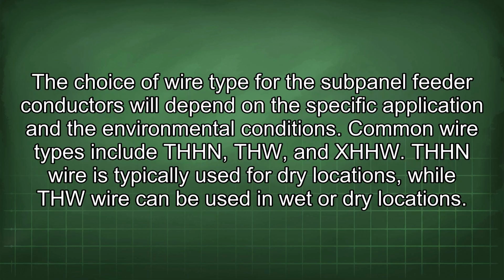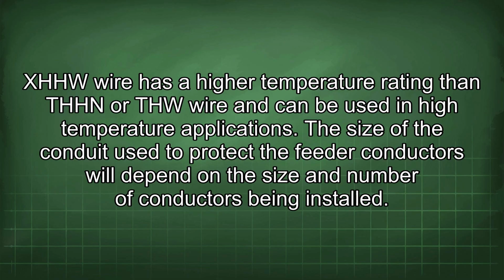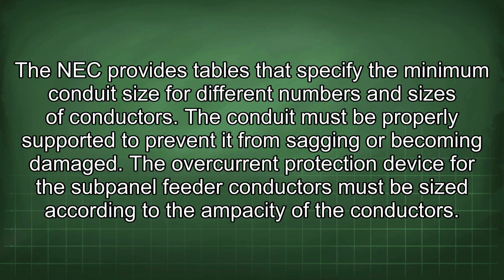The choice of wire type for the subpanel feeder conductors will depend on the specific application and the environmental conditions. Common wire types include THHN, THW, and XHHW. THHN wire is typically used for dry locations, while THW wire can be used in wet or dry locations. XHHW wire has a higher temperature rating than THHN or THW wire and can be used in high temperature applications. The size of the conduit used to protect the feeder conductors will depend on the size and number of conductors being installed. The NEC provides tables that specify the minimum conduit size for different numbers and sizes of conductors. The conduit must be properly supported to prevent it from sagging or becoming damaged.